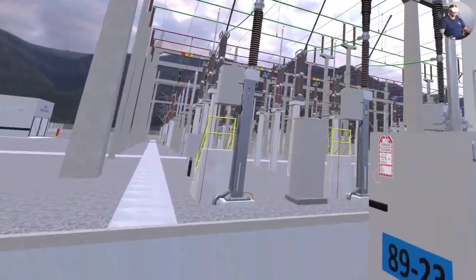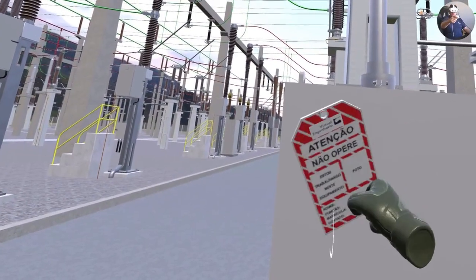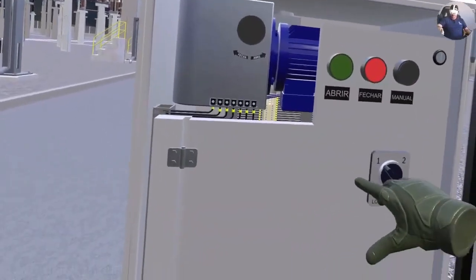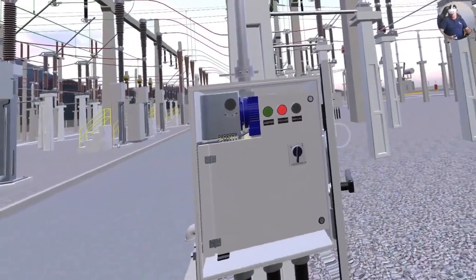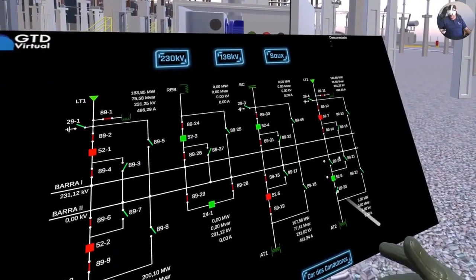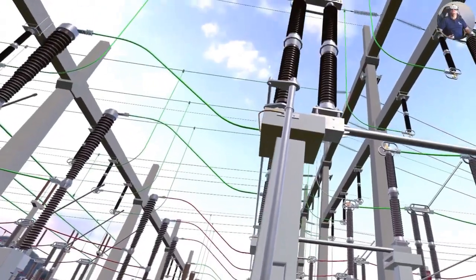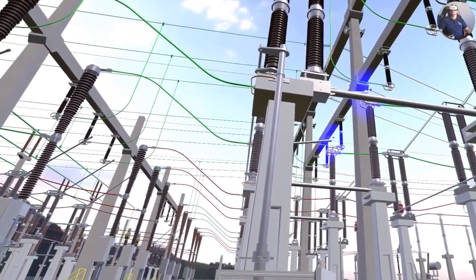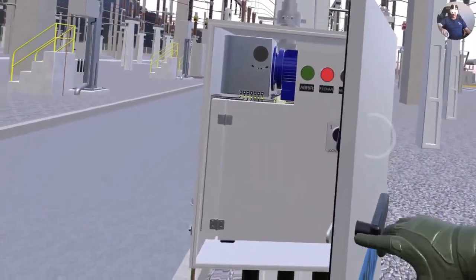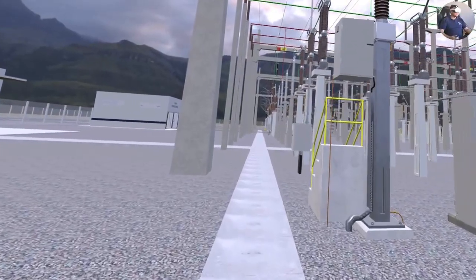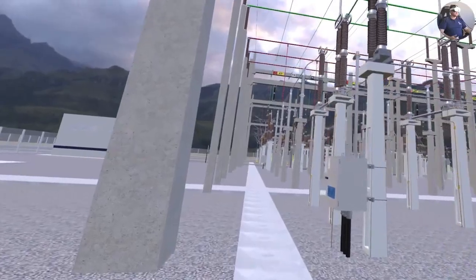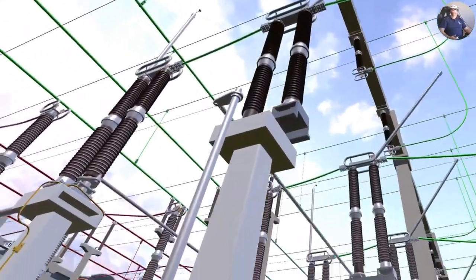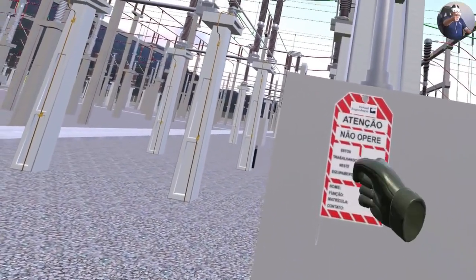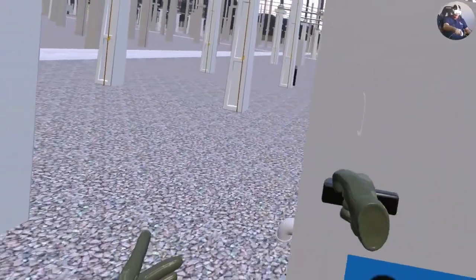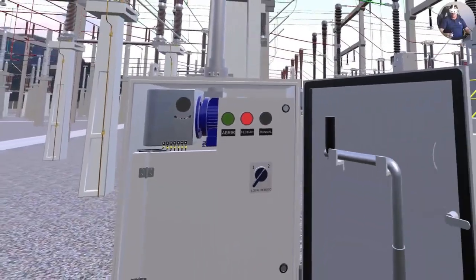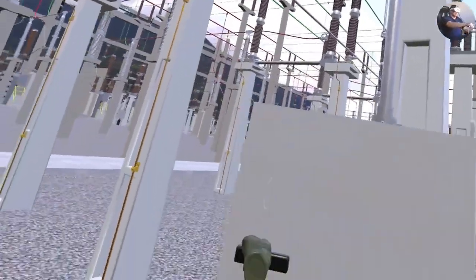This other disconnect switch here for the breaker. Let's remove the safety tag. And let's switch it to remote here. And let's give the command here, which is 8923. Switch closed. Let's close the panel. This disconnect switch here is for bus 2. We're going to return this function to bus 1. Let's remove the tag here. Let's switch it to remote if you do not mind. Let's close the panel right now, just to be sure. And this one remains open, right?